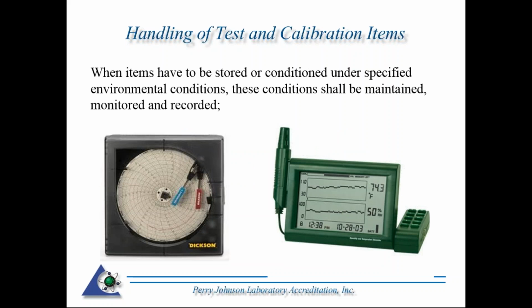All right, we're talking about the ambient conditions of your laboratory. So when items have to be stored or conditioned under specified environmental conditions, these conditions shall be maintained, monitored, and recorded. Hence, in the calibration world, they may specify calibrations are to take place at 20 degrees C, for example, plus or minus 2 degrees C, with no more than a half a degree C, that's degrees Celsius, per hour. This is an example of what I'm referring to here.